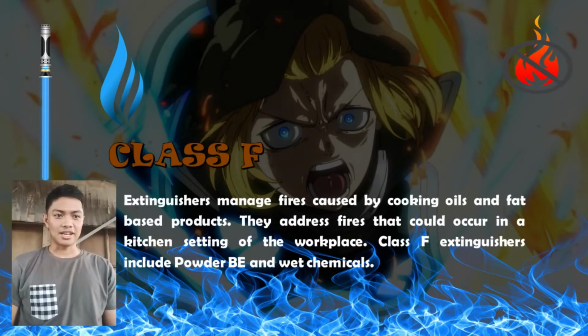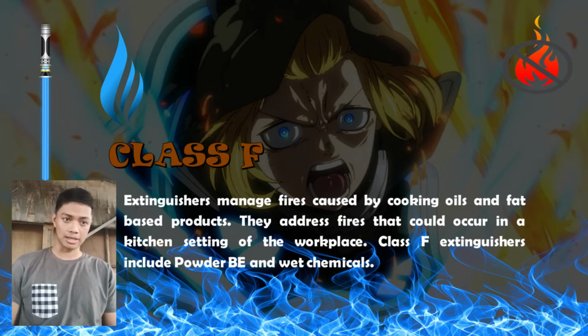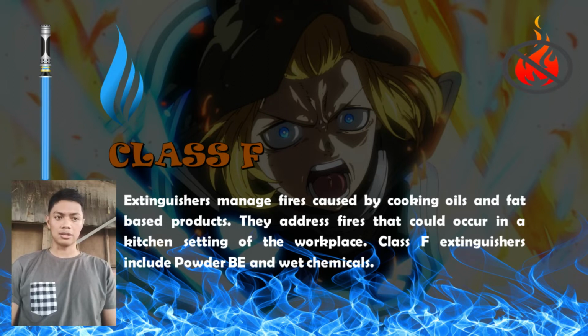And lastly, Class F fire extinguishers manage fires caused by cooking oils and fat-based products. They address fires that could occur in the kitchen setting of the workplace. Class F extinguishers include powder BE and wet chemicals. This extinguisher is commonly used in kitchens and canteens.